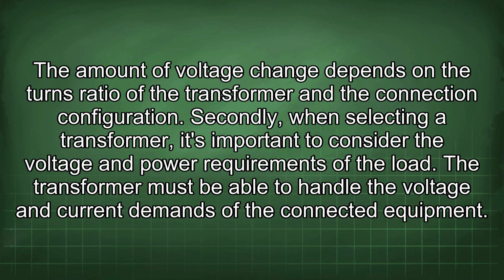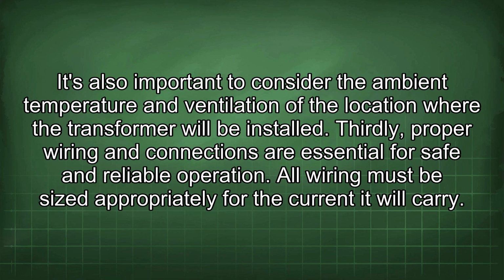Secondly, when selecting a transformer, it's important to consider the voltage and power requirements of the load. The transformer must be able to handle the voltage and current demands of the connected equipment. It's also important to consider the ambient temperature and ventilation of the location where the transformer will be installed.